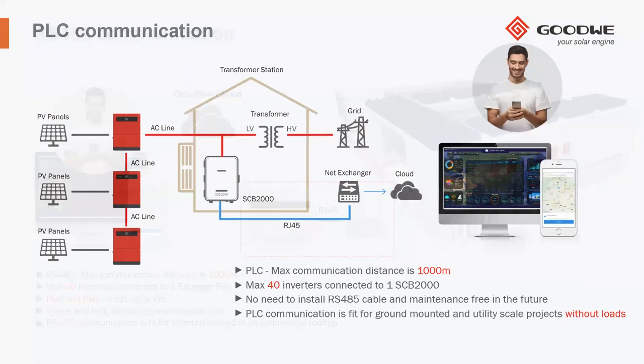Another possibility is to use PLC, so the data are transferred through the power line. This is extremely important, especially for a large-scale installation, because you can save on the cost of setting up an alternative line of communication. You can use the power cable for that, so it's a big saving. In this case, we recommend the SCB2000 connection and communication box. Through the AC line, the monitoring data are transferred to the SCB2000, and through RJ45 to the net exchanger, to the cloud and to our monitoring system, called SEMS, that we will see later on. In this case, the PLC maximum communication distance is 1 kilometer, and up to 40 inverters can be connected to this communication box.